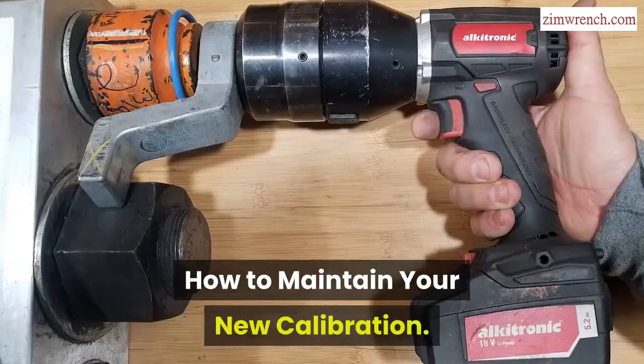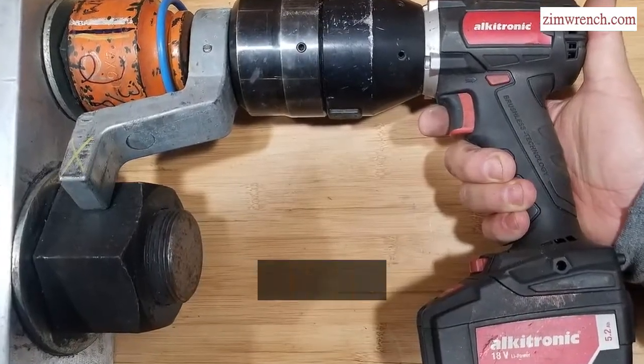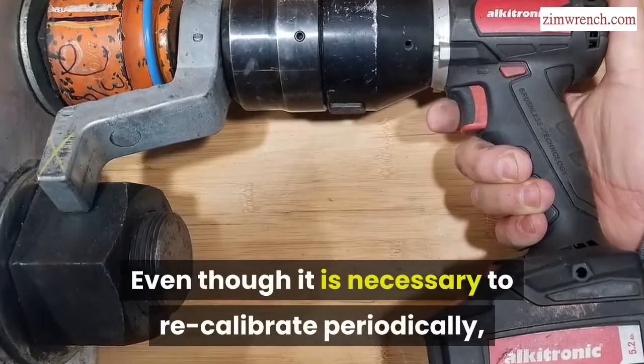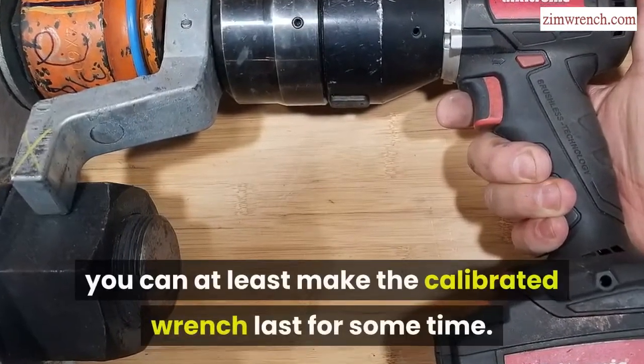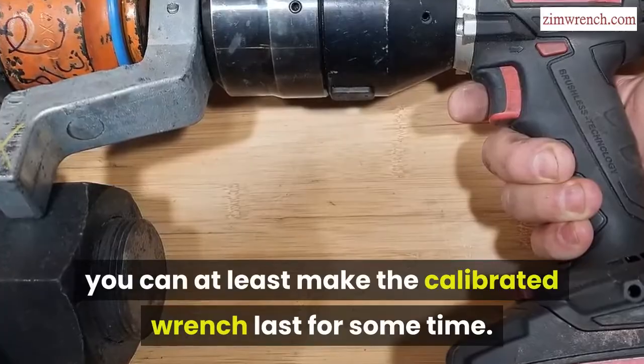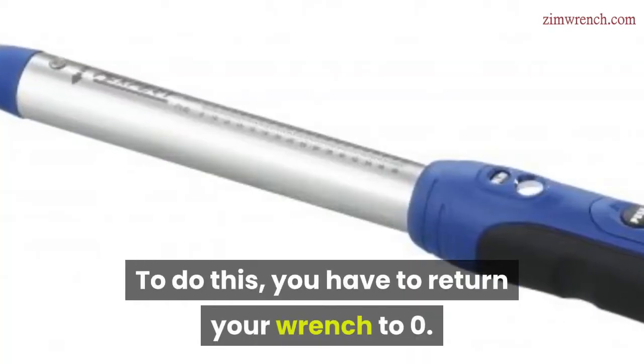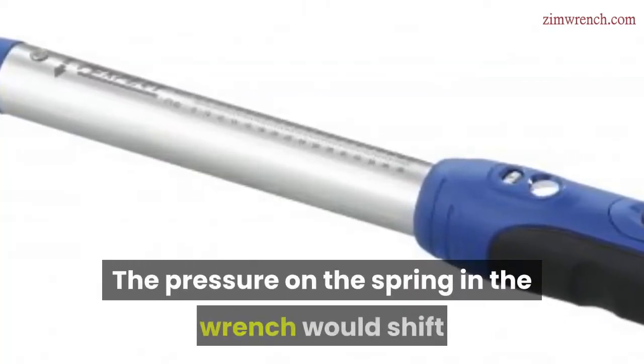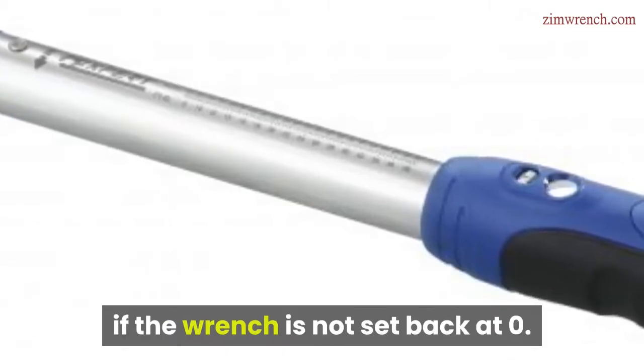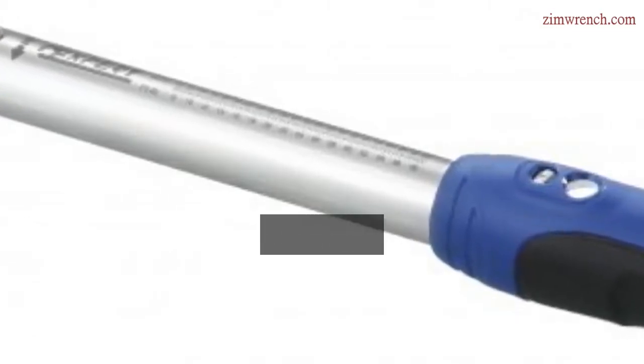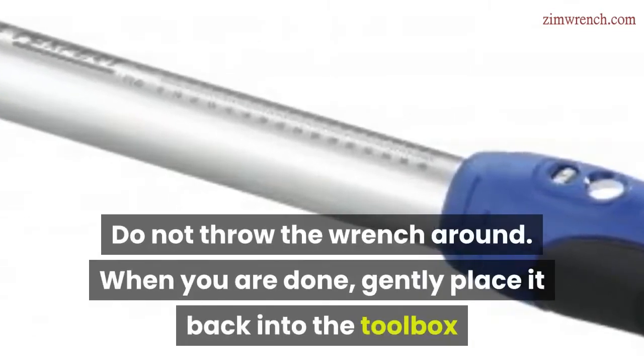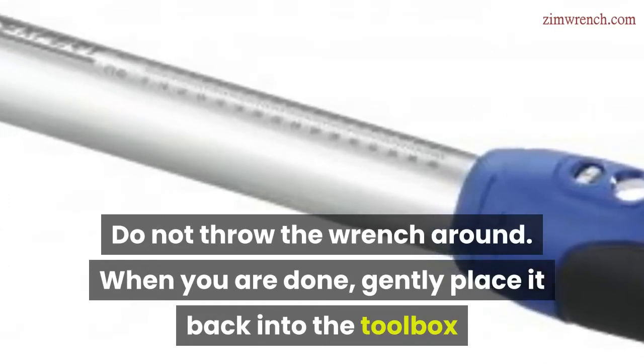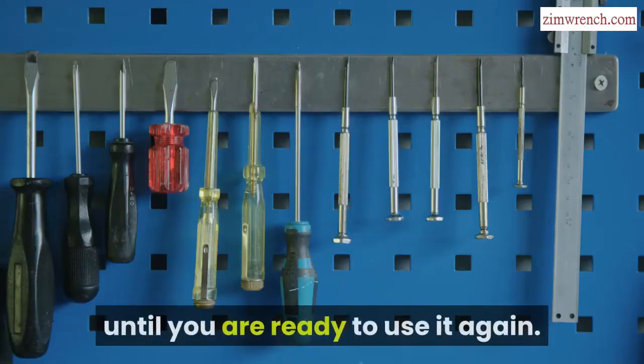How to maintain your new calibration. Even though it is necessary to recalibrate periodically, you can at least make the calibrated wrench last for some time. To do this, you have to return your wrench to zero. The pressure on the spring in the wrench would shift if the wrench is not set back at zero. Do not throw the wrench around. When you are done, gently place it back into the toolbox until you are ready to use it again.